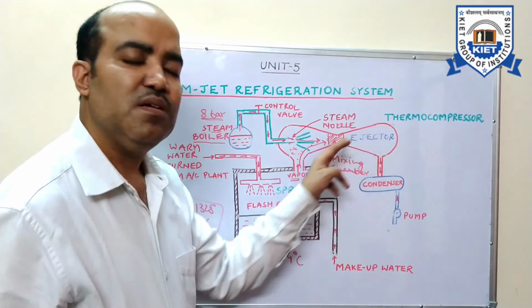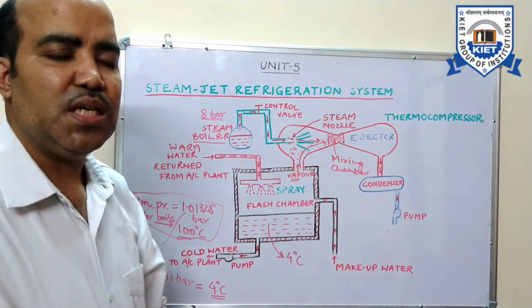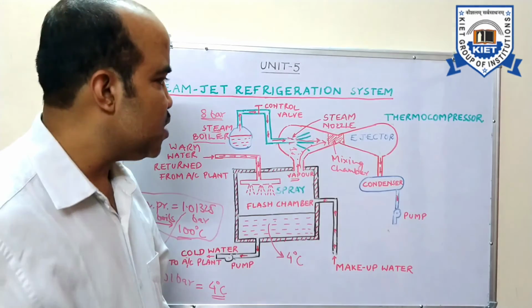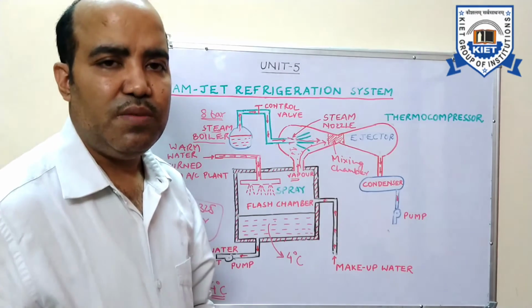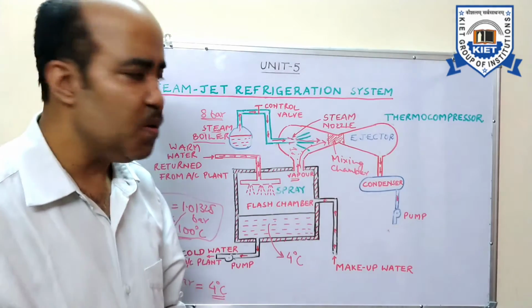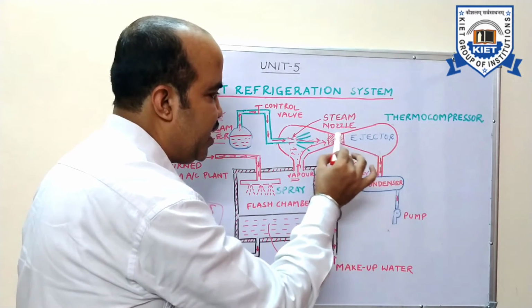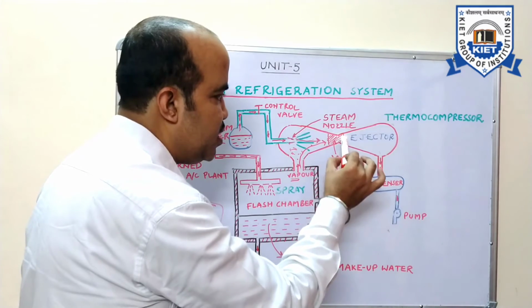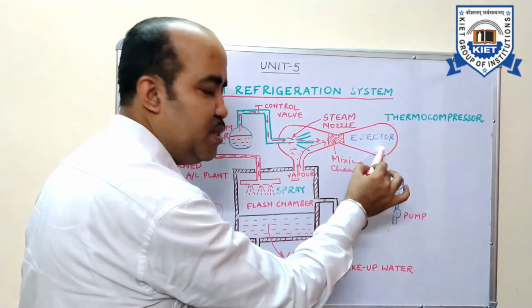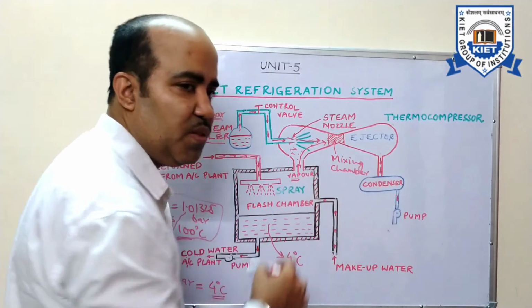And finally, that part of the ejector where the increase in area and consequently the change of velocity back into pressure takes place is the diffusing section.